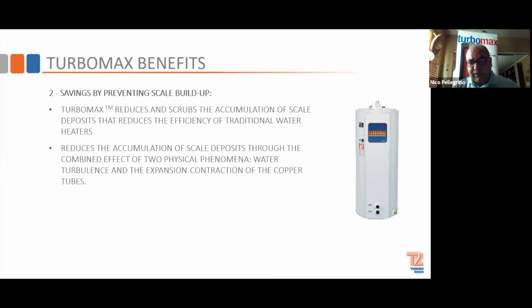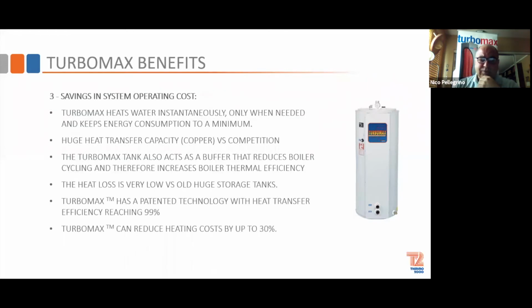The coil is designed to expand and contract. It's like an accordion. So if there is a little bit of scale buildup, it will fall down into the bottom of the tank, and then you can clean it. We do have a higher pressure drop through the coil, and that's so that we can scrub the inside of the coil so that there is no scale buildup on the inside. So basically, because we're copper, we have a high rate of transfer, and we'll just go over that a little bit. And also, you have a built-in buffer tank for your boiler, because you have a vessel full of boiler water that eliminates the boiler from cycling if it's on some small loads.